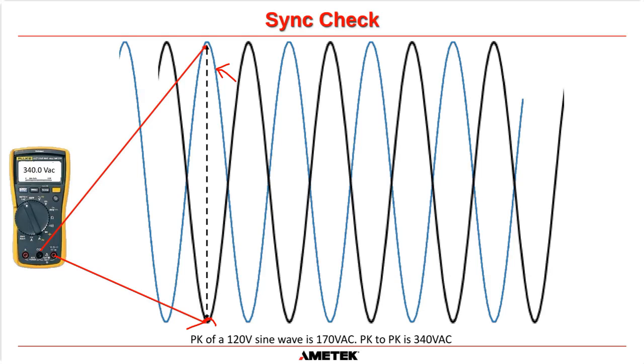And therefore, if you parallel those two together at that point, there is going to be a huge amount of circulating current, because basically paralleling them together is a short circuit. And a high voltage across a very low resistance creates a lot of current. So that is why it's important to be in sync when you transfer a system to bypass.